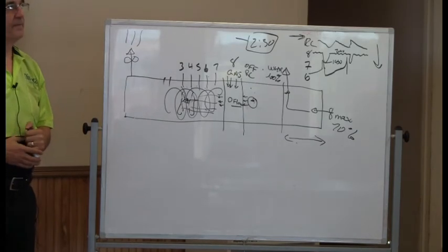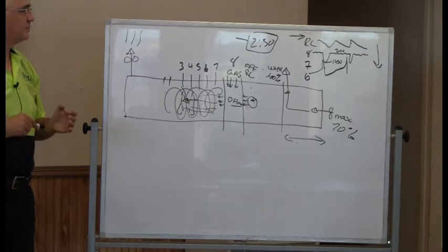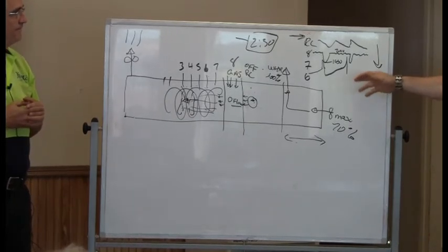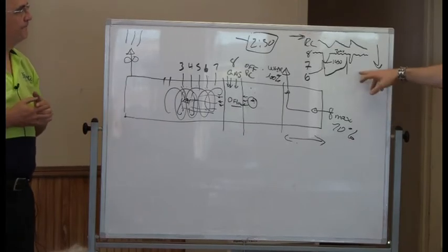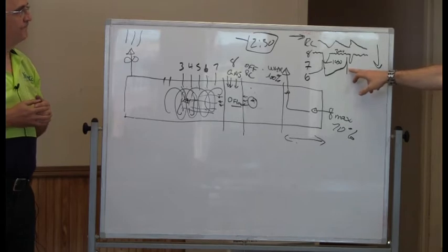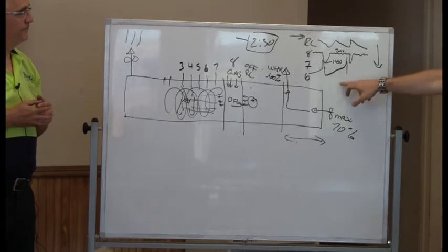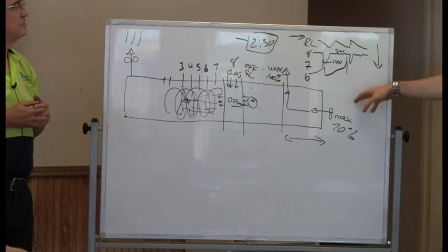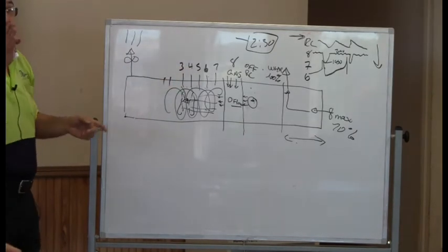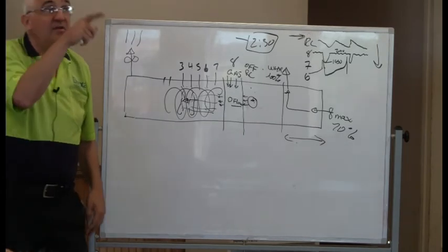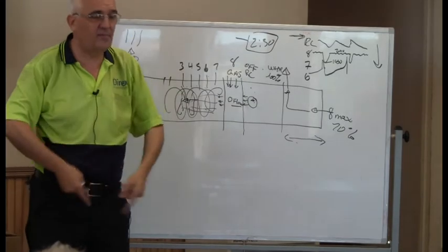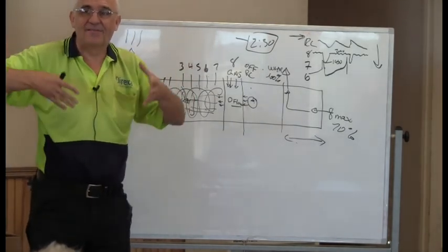So right now we're seeing that most of our flashing burns up in 7 and 6. Okay. And then we do get some residual smoke after that. And so basically then, okay, we let 7 alone, right? Mm-hmm. It doesn't come on. 6 and 5. And then 6, 5, 4. As far as you can go, as long as you see the smoke and you see a flame occurring, and it's funny when you do that because you see a flame happening at the burner.